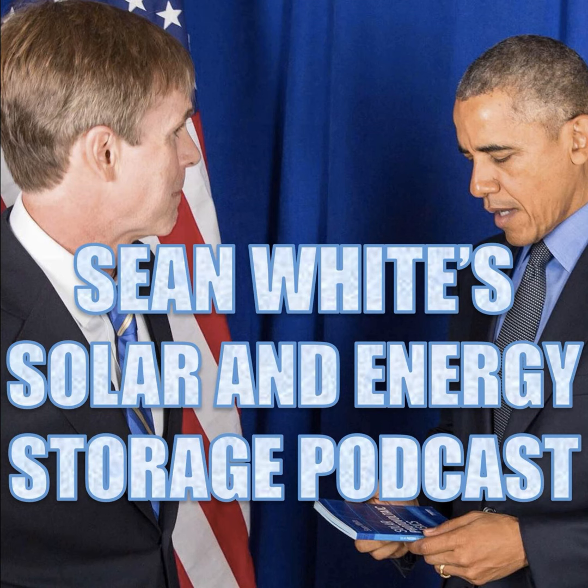Power is the inverter rating, usually, of an energy storage system. Power times time equals energy—that's a lot of times the batteries you'll have in an energy storage system, that's how much energy you have. The inverter is rated in watts, kilowatts, megawatts. The batteries we talk about in amp hours times volts, or watt hours—watt hours, kilowatt hours, and megawatt hours.